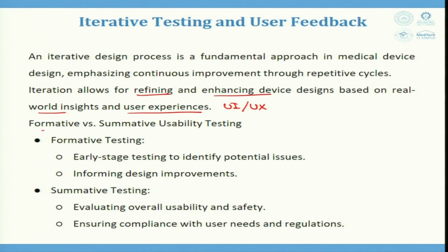So, it could be formative or summative. Formative versus summative usability testing, how is it compared? Formative testing is something where early stage testing is taken care of to identify potential issues. It is informing design improvements only. Summative testing is one where evaluating overall usability and safety is concerned. Now, ensuring compliance with user needs and regulation is taken care of in the summative testing.